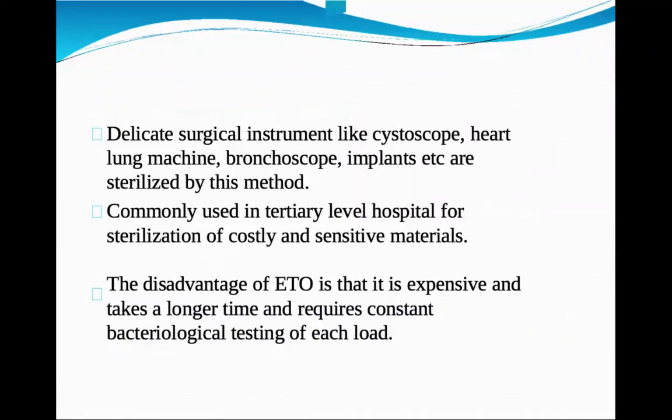Delicate surgical instruments like cystoscopes, heart-lung machines, bronchoscopes and implants are sterilized by this method. In tertiary level hospitals, it is used for sterilization of costly and sensitive materials. The disadvantage of ETO is that it is expensive, takes a longer time, and requires constant bacteriological testing of each load.